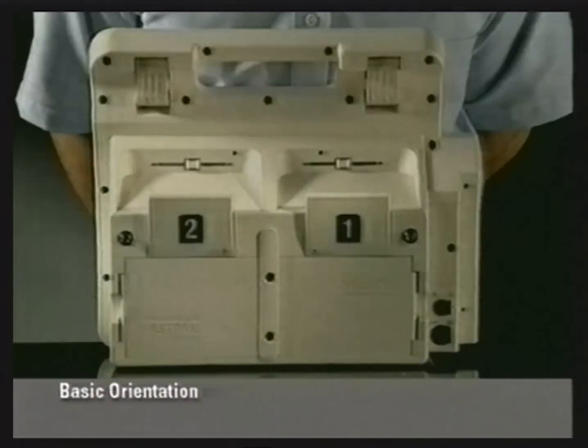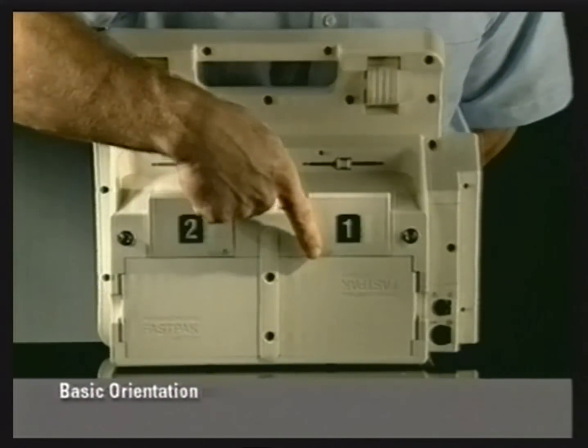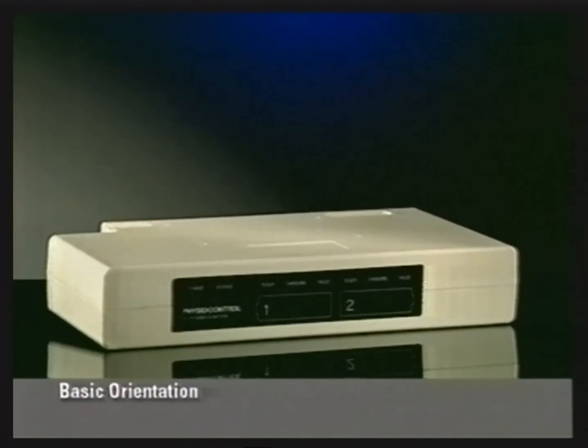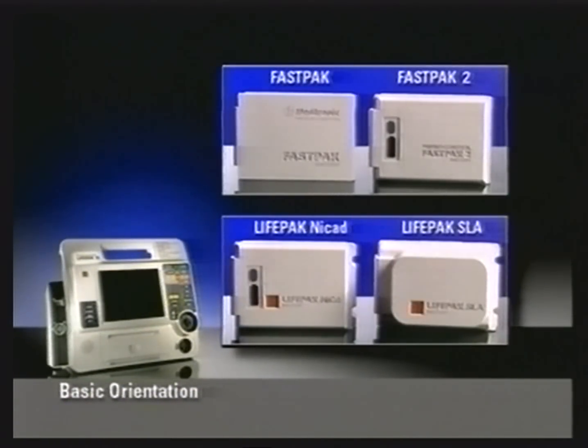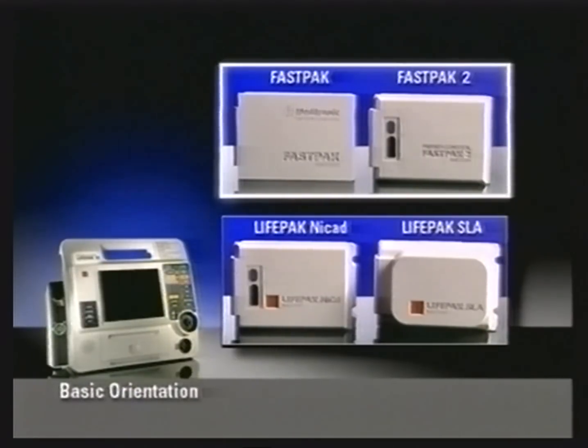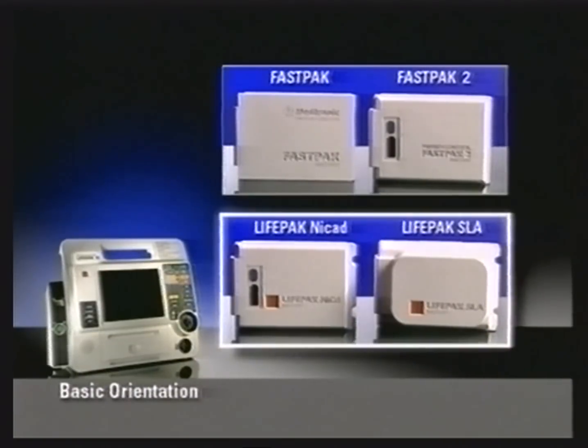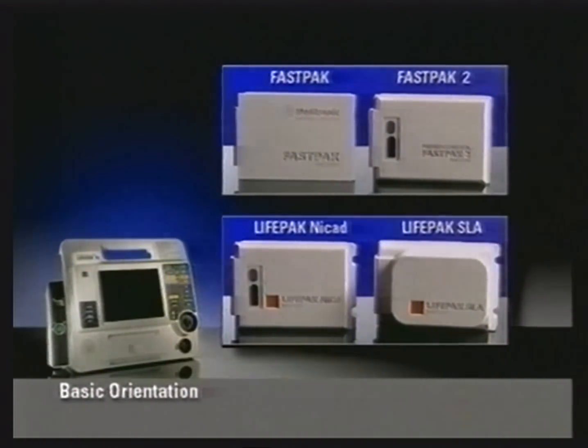The Lifepak 12 defibrillator monitor is powered by 2 batteries, or the Physio Control AC and DC power adapters. 4 types of batteries may be used. FastPak batteries are a nickel-cadmium chemistry and do not communicate to the monitor about battery charge level. Lifepak batteries can communicate battery charge level to the monitor.